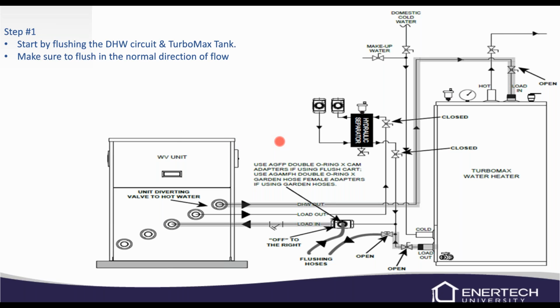So make sure to flush in the normal direction of flow here, because we've got a strainer on the load end as well, because we've got a braze plate there. So we're going to flush in through there. We'll flush through the tank and then back to the unit, or back to your flush cart and back through. That probably really won't take real long, depending on how far away your TurboMax tank is, but it won't be too far away. So it shouldn't take too long.